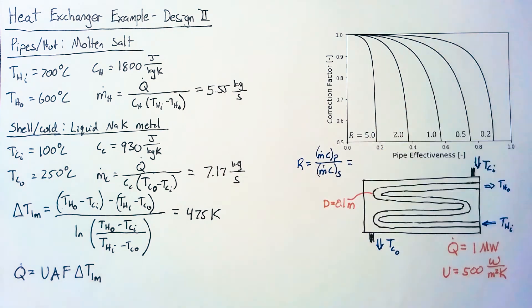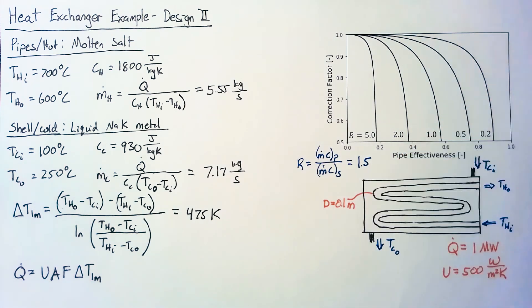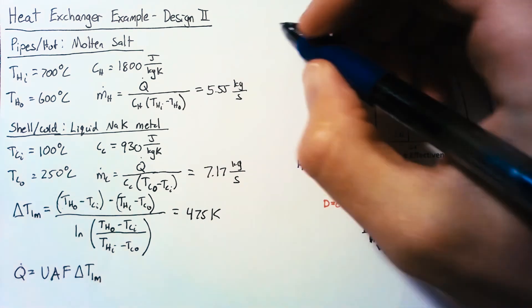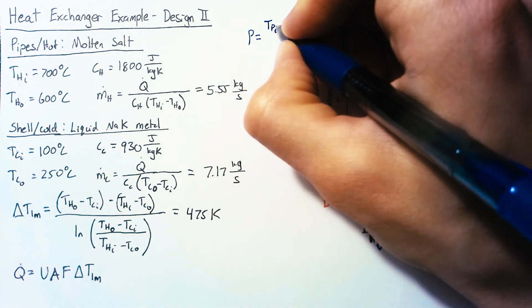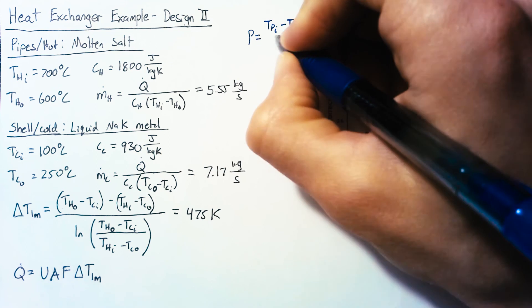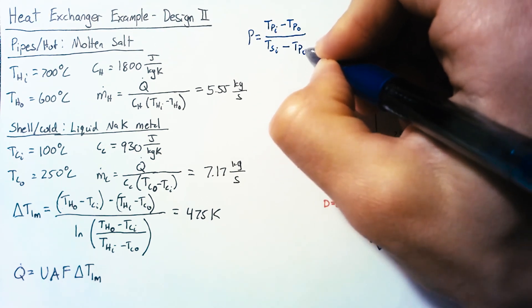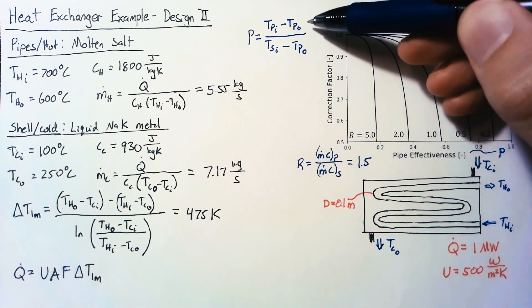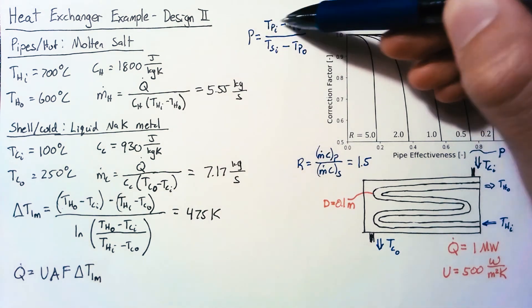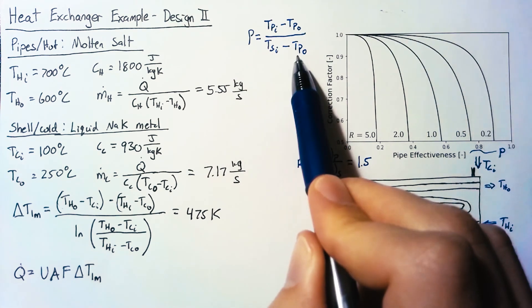Our R value is going to be the ratio of our total heat capacity for the pipe divided by that in the shell. And for our example here, that ratio is 1.5. Now the pipe effectiveness, I'm going to call P, and P is equal to the pipe inlet temperature minus the pipe outlet temperature divided by the shell inlet temperature minus the pipe outlet temperature. I'm calling this the effectiveness because this is essentially a ratio of the total heat transfer in the pipe compared to the maximum possible heat transfer in the pipe.